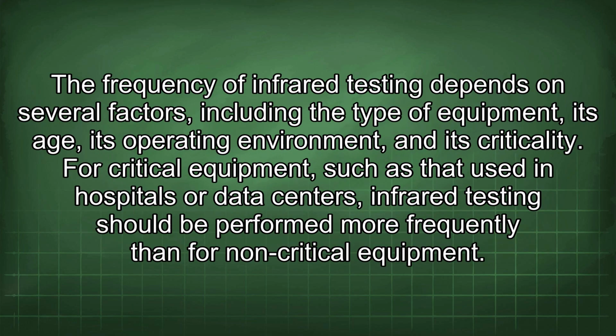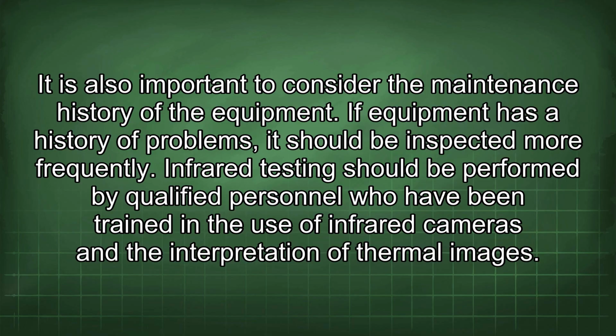The frequency of infrared testing depends on several factors, including the type of equipment, its age, its operating environment, and its criticality. For critical equipment, such as that used in hospitals or data centers, infrared testing should be performed more frequently than for non-critical equipment. It is also important to consider the maintenance history of the equipment. If equipment has a history of problems, it should be inspected more frequently.